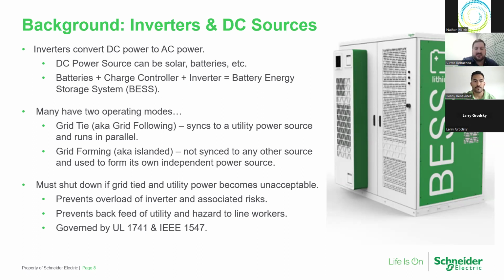The reason it has to do this is for the safety of anybody who's working on the power lines. Say it is grid tied to utility and the utility goes down and the inverter is backfeeding the system. It could hurt someone who's trying to repair whatever caused the outage, and it could also result in damage to the inverter itself. At that point, your grid, which was a source, essentially becomes a load instead of a source.